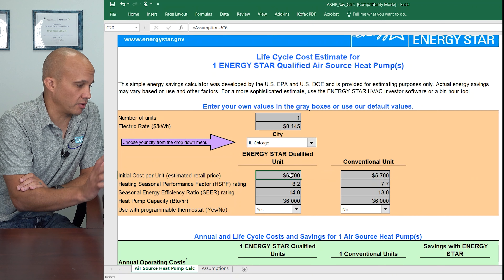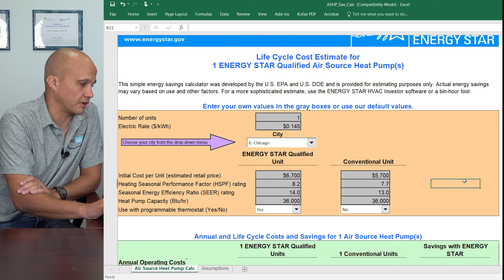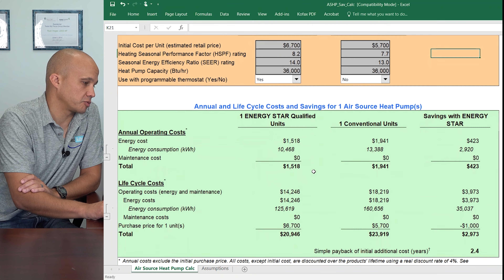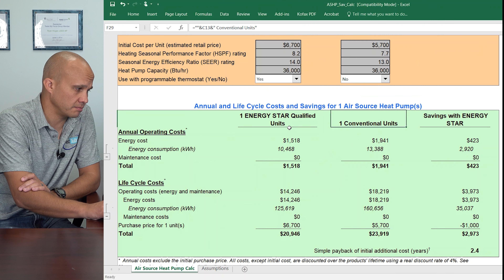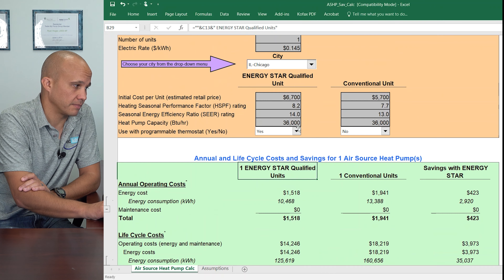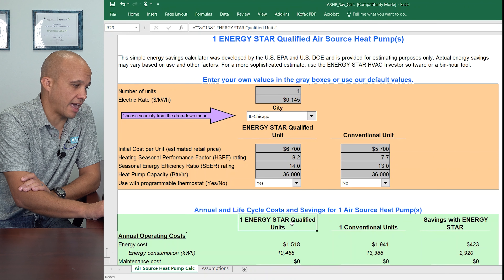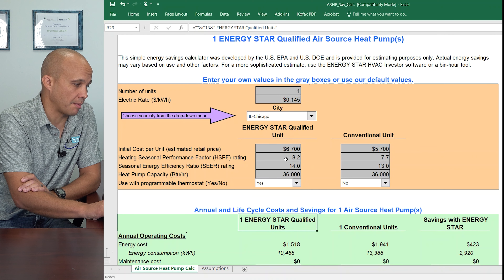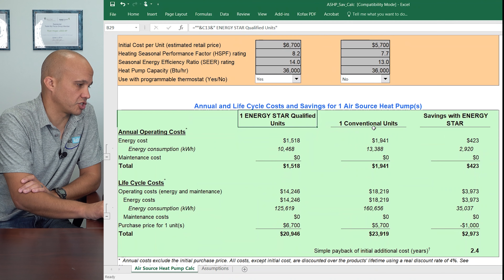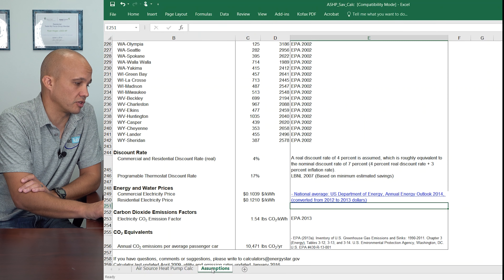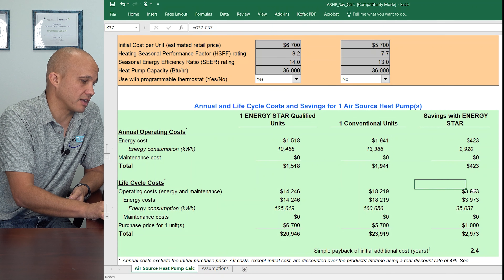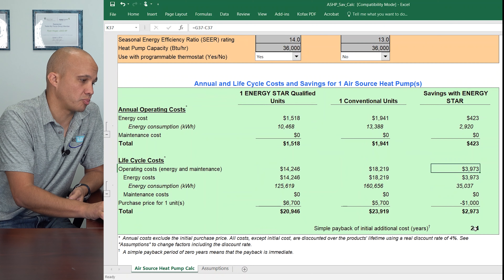The cost I'm going to leave at the default for right now. I have no idea what things really cost when a homeowner buys something. So you just do that little bit of information in that orangish section and it'll spit out your answer in the green section. Here's my regular system and here's my new proposed system. So it's going to save me $423 a year, and over the life cycle cost — which uses a 12-year life cycle calculation from the assumptions page — it's going to save me almost $4,000 for this particular customer. And that's a 2.4 year payback.